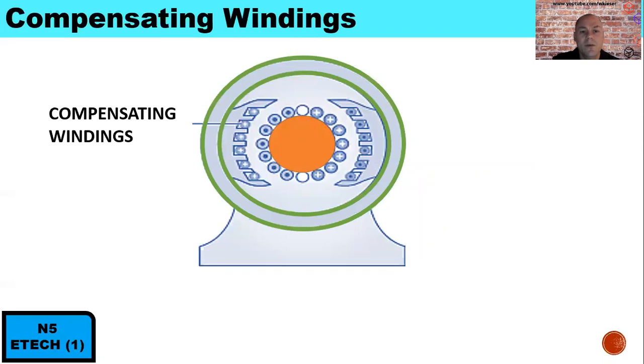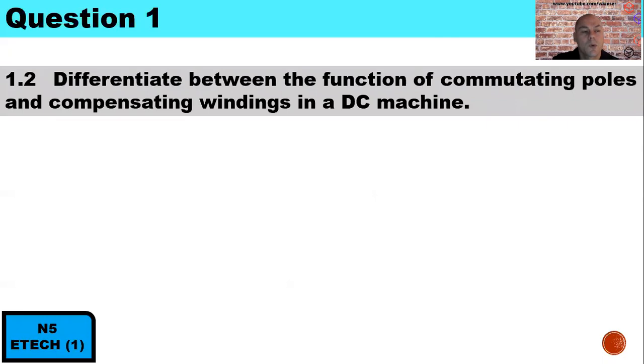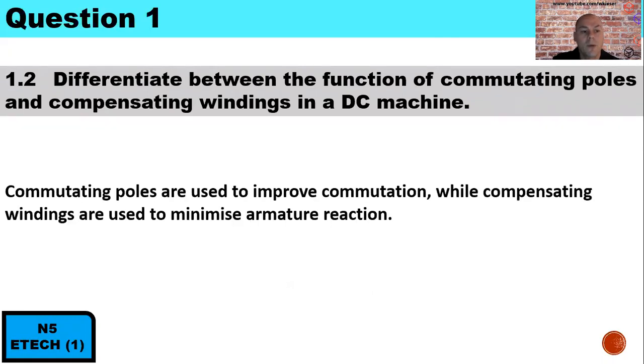Our compensating windings are slotted inside the pole shoes. Question 1.2: Differentiate between the function of commutating poles and compensating windings in a DC machine. Commutating poles are used to improve commutation, while compensating windings are used to minimize armature reaction.